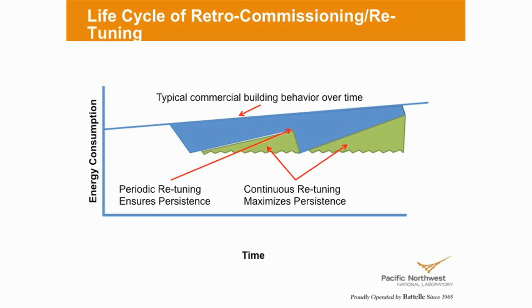So what we're trying to do with retuning is find a way to fill that gap. With continuous retuning, someone will say, well how often do I have to retune or tune my building? We really don't tell you that. What we'd say is tuning, retuning, is basically an internal process to your organization - continually looking at the meter data, your HVAC systems, your controls, how you maintain and operate your buildings, asking if there's something that indicates things are starting to get out of bounds and you need to go look. So really what retuning is, it's a systematic process to identify and correct operational problems that lead to energy waste. That's, in a nutshell, really what it is.